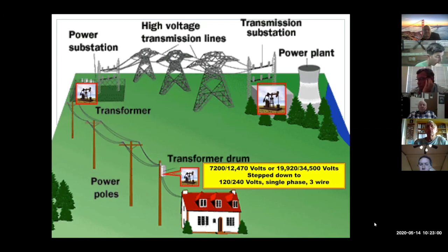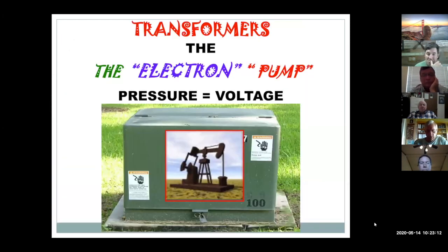Okay, all right, here's a pump that's sitting out in the yard here in Sienna Plantation area in Houston. This transformer's a pad mount. It's sitting out in this guy's yard. Big houses with big yards, swimming pools about 100 yards away from it. If you'll see on this transformer, it's got 100. That's its kVA, kilovolt amps output. This is its output of the transformer.